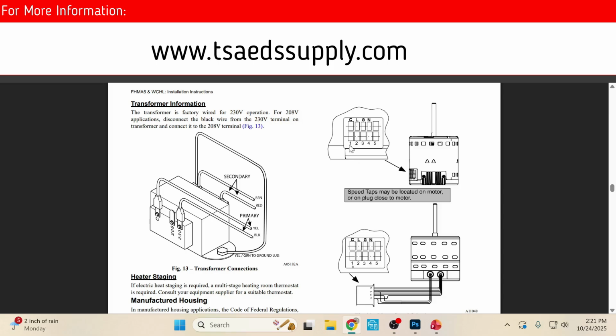The other part of that, if you'll see right here, you got speed tap 1, 2, 3, 4, and 5. Now, 4 is always designated for the heat because 3 and 4 are the exact same speed and RPM. So you can put your blue wire on 3 and your white wire on 4, and they're both in high speed. Now, it'll come from the factory set in 2. And when we looked at the unit out there in the shop, it is a 1.5 ton, which means you put it in because you need 600 CFM. Now, just because you buy a unit right out of the box doesn't mean it's going to have 600 CFM. So you're going to have to be able to tell it what capacity you want it to run at.